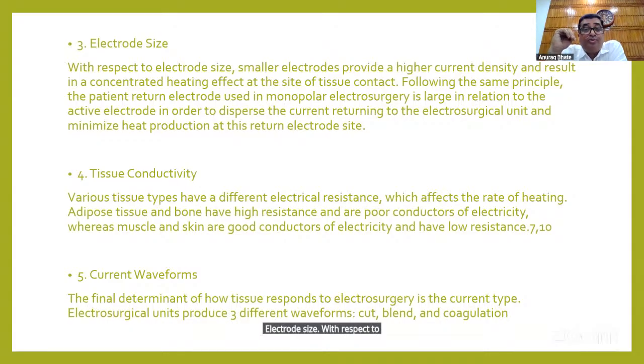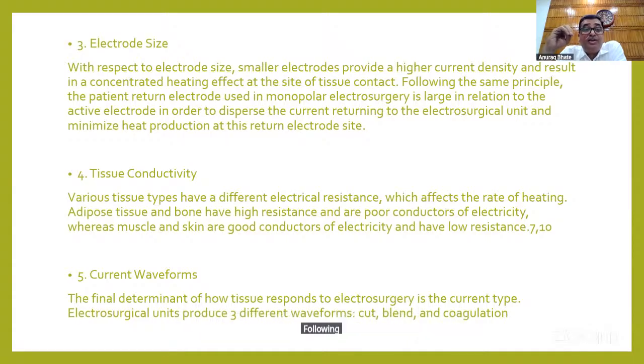Electrode size. With respect to electrode size, a small electrode provides a higher current density and results in a concentrated heating effect at the site of tissue contact. Following the same principle, the patient return electrode used in monopolar electrosurgery is large in relation to the active electrode in order to disperse the current returning to the ESU and minimize heat production. That is why the electrode we use is smaller and the patient plate is much bigger, because the amount of current it will take out of the body has to be reciprocal, otherwise there will be a leakage of current.